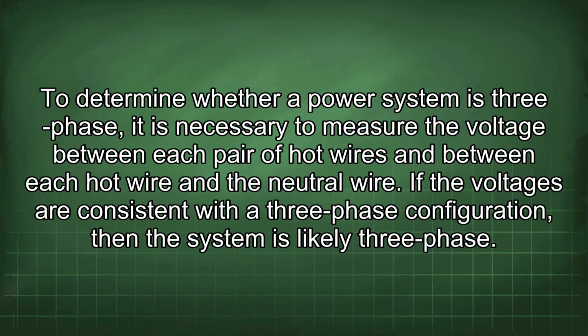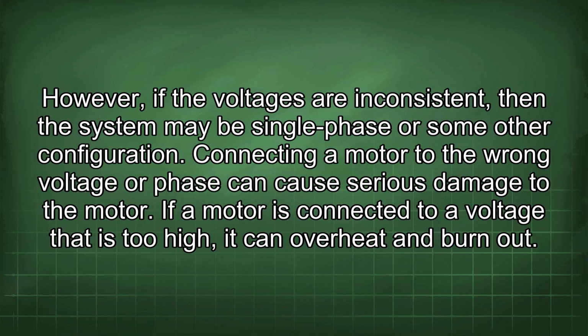To determine whether a power system is three-phase, it is necessary to measure the voltage between each pair of hot wires and between each hot wire and the neutral wire. If the voltages are consistent with a three-phase configuration, then the system is likely three-phase. However, if the voltages are inconsistent, then the system may be single-phase or some other configuration.